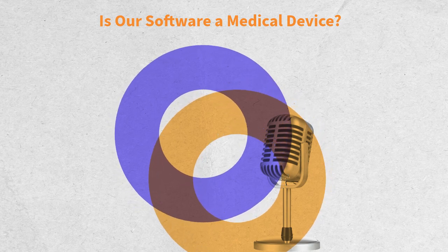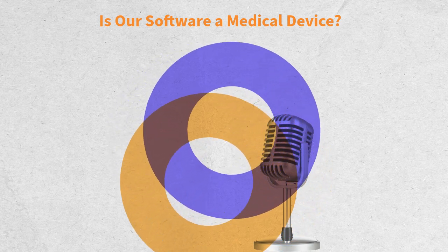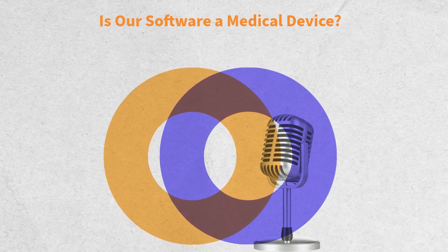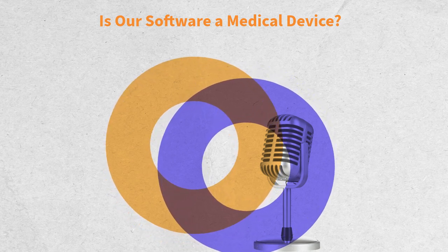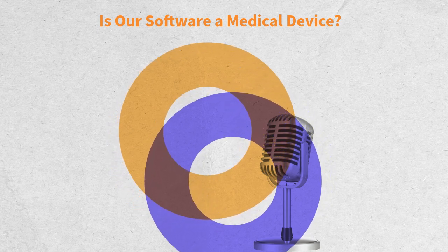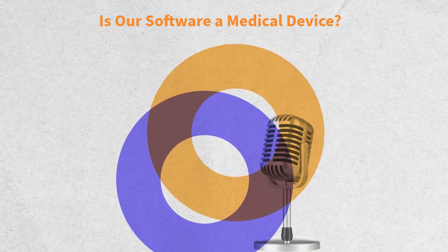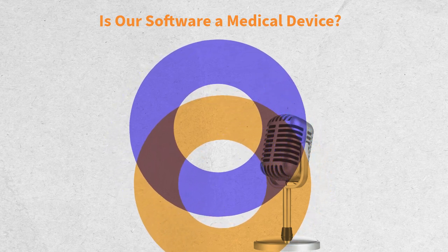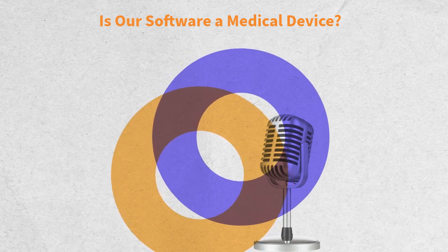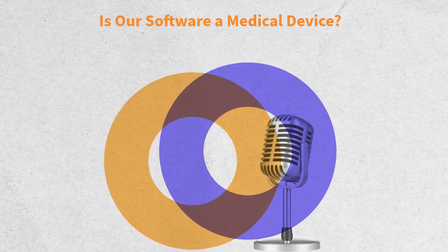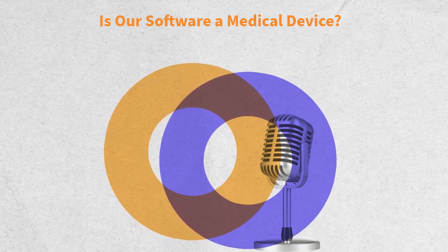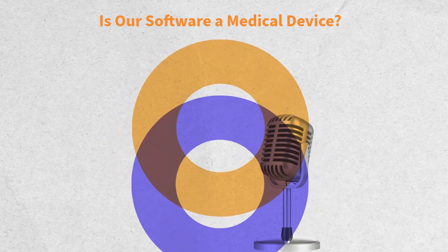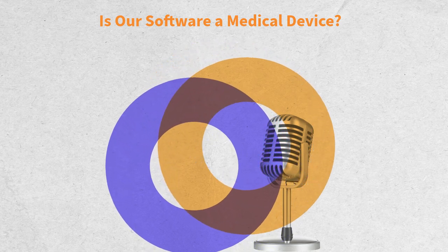Is there any guideline to establish if a software is a medical device? Yes. The MDCG, Medical Device Coordination Group, 2019-11, is the most complete official guideline to understand how to interpret the regulations and determine whether your software is an MD. It contains flowcharts and clear criteria to understand classification. The guidelines MDCG 2023-4 and MDCG 2019-16 Revision 1 are also available.